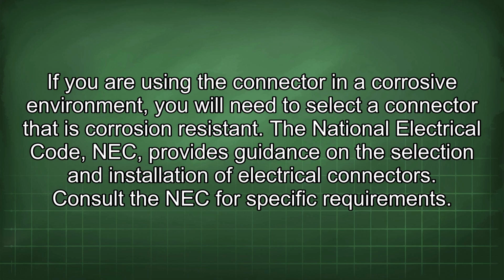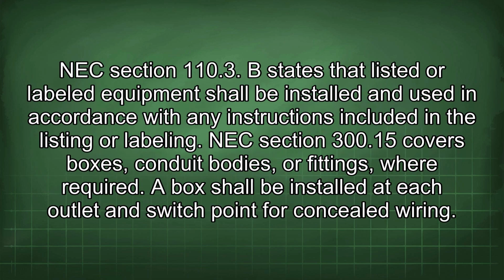The National Electrical Code, NEC, provides guidance on the selection and installation of electrical connectors. Consult the NEC for specific requirements. NEC Section 110.3(B) states that listed or labeled equipment shall be installed and used in accordance with any instructions included in the listing or labeling. NEC Section 300.15 covers boxes, conduit bodies, or fittings, where required. A box shall be installed at each outlet and switch point for concealed wiring.